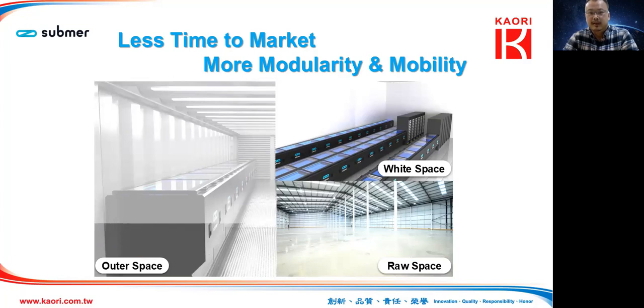Another advantage I see is less time to market, and more modularity and mobility. In traditional air cool scenarios, once you have data center raw space, you need to set up the raised floor and air containment for the air to flow in the right direction. But with the immersion cool tank, you don't really need the raised floor or air containment, because the entire tank is a predefined environment for IT equipment, so you can deploy pretty much to a raw space.